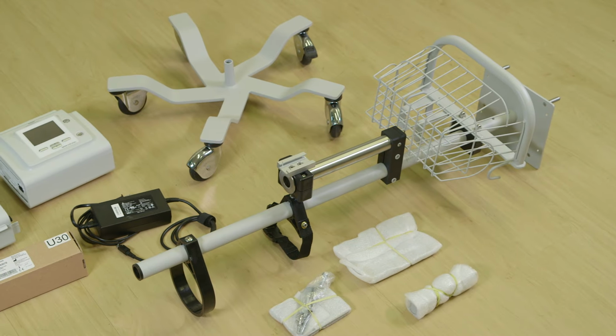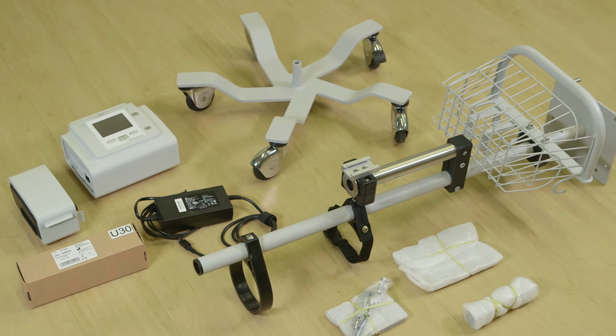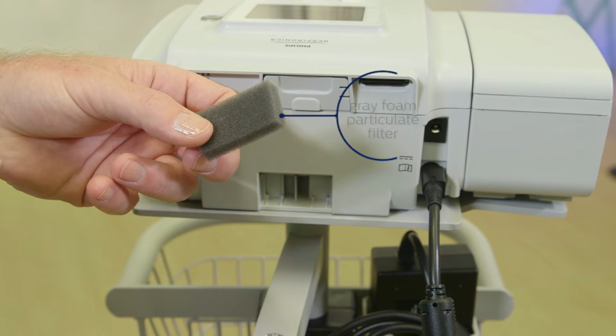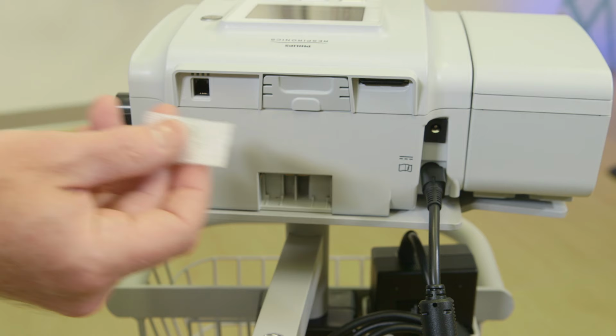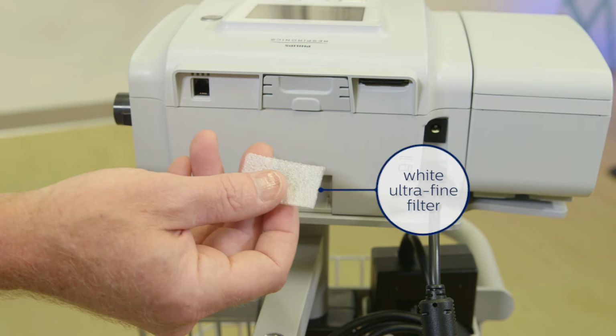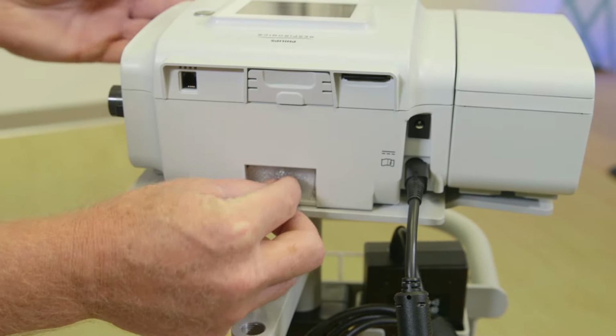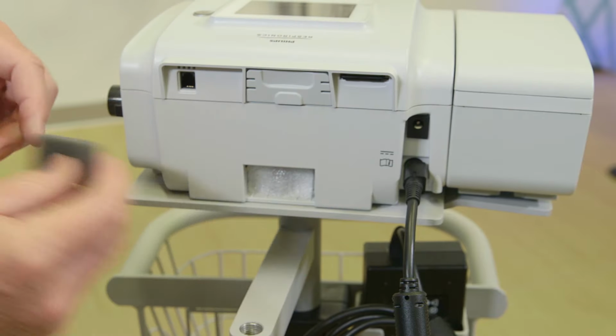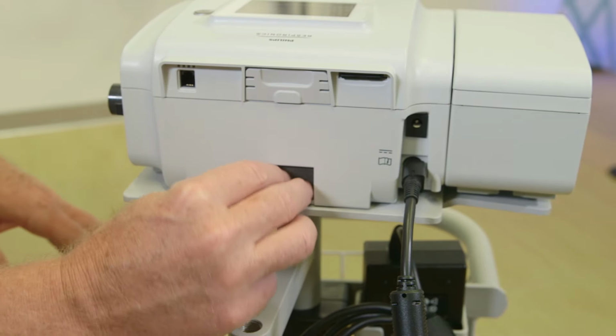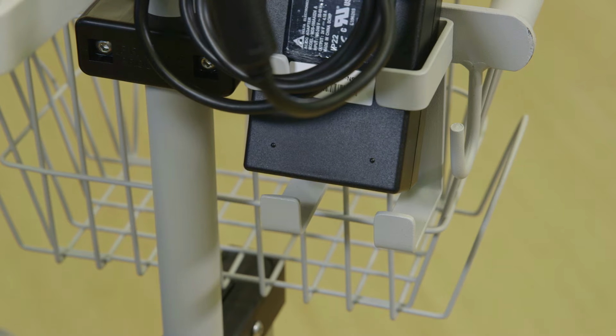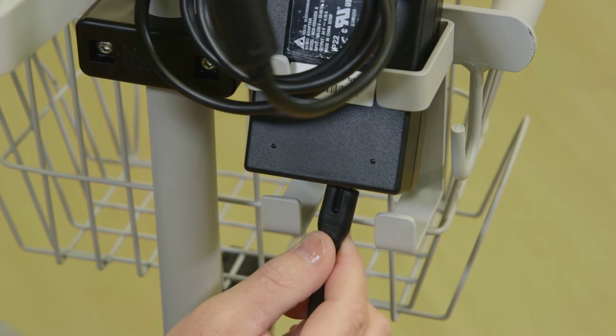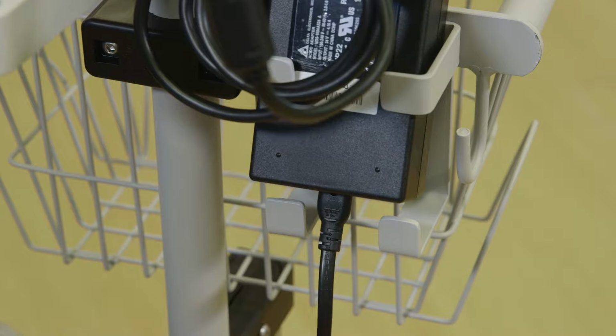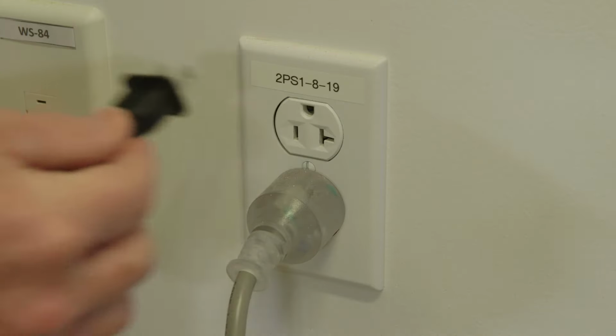When unboxing the V30, you'll find a few items needed to get the device patient-ready, including a reusable gray foam particulate filter, as well as a white ultrafine filter that is disposable. If these filters are not already installed when you receive your device, you will need to insert the white ultrafine filter here, and then the gray filter like this. If you're using AC power, plug the socket end of the power cord into the power supply and the pronged end of the power cord into an electrical outlet.